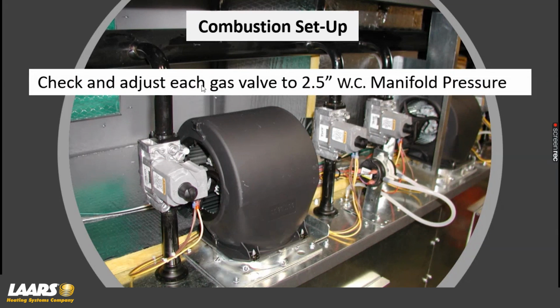So we're going to go through and check each gas valve and adjust them if needed at 2.5 inches of water column manifold pressure. That's downstream pressure, okay? And you'll see this in the video. So you're going to have another test plug like this on the bottom, and that's where you're going to put your manometer in and double check that as well.